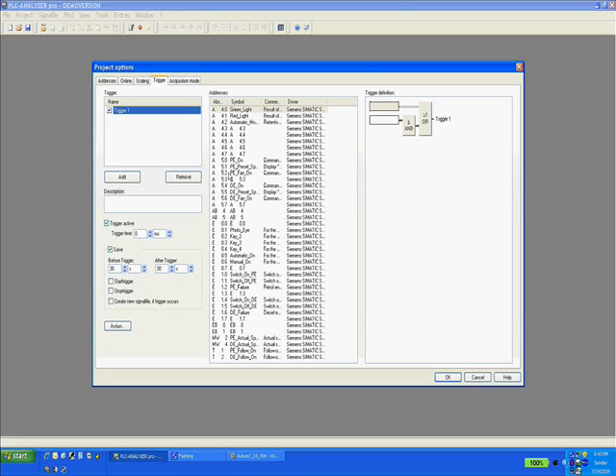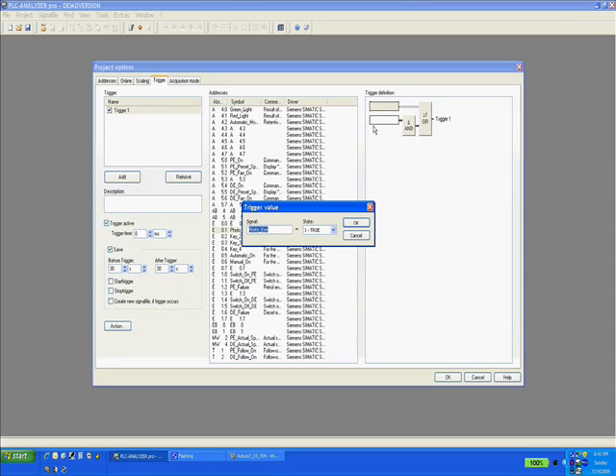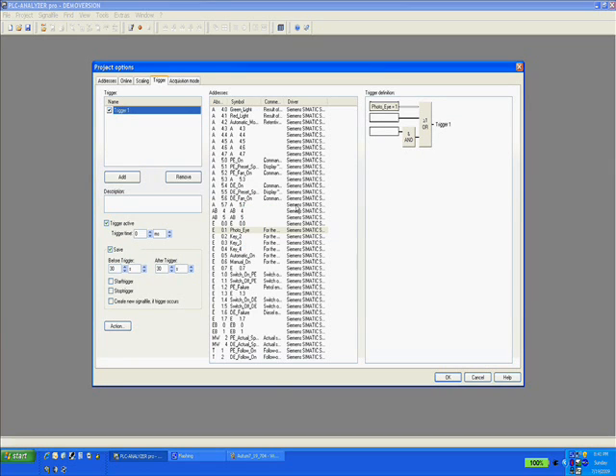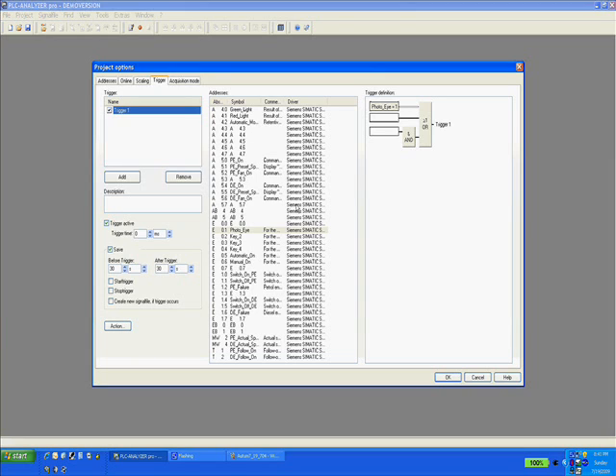An example would be when you are working on a faulty diverting station on a conveyor system. You realize that it rejects both the good and the bad products. You can pick a signal such as a photo eye and drop it in the trigger definition window. Once you run the software and a good product arrives at the photo eye, the system starts recording and you can check and analyze all the signals from the diverting station and find the bad components such as a faulty photo eye or a bad barcode reader.